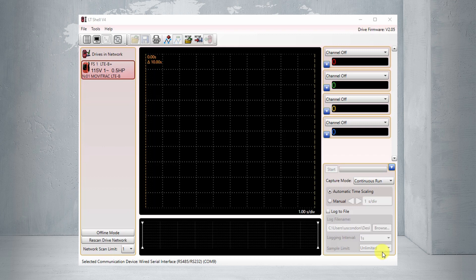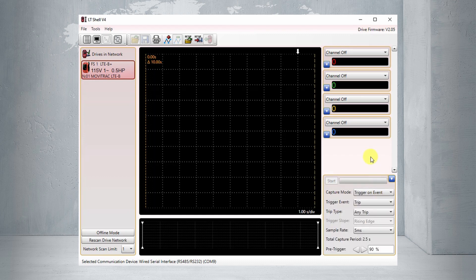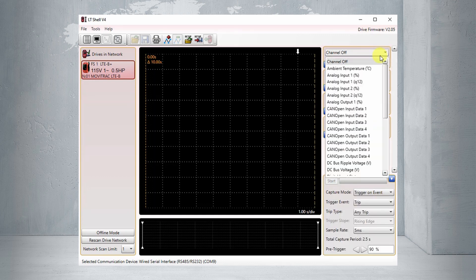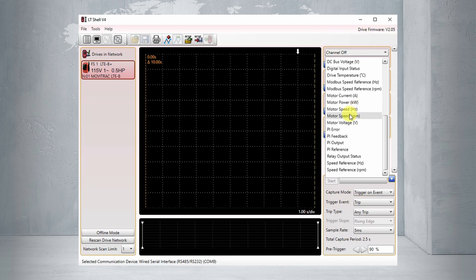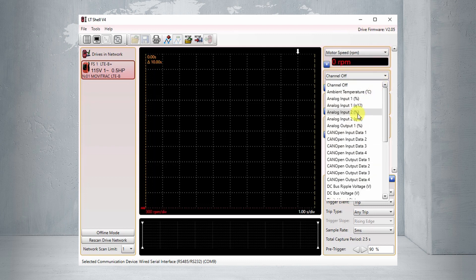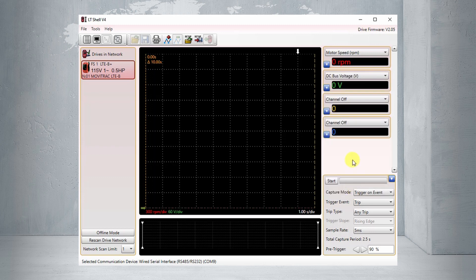Let's do a number of triggered captures and see how they differ. We're going to do three different kinds of triggered capture. We're back in the scope; no parameters on the VFD have changed. We need to change it to trigger on event mode and pick some channels. Let's use motor speed again for our first value, and the DC link voltage for our second value.